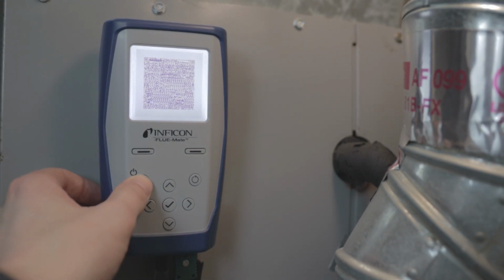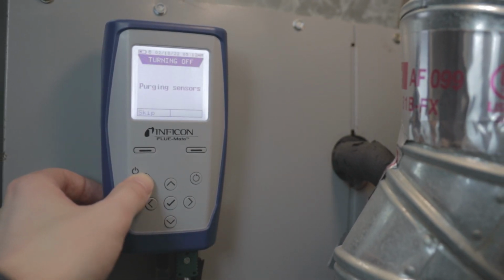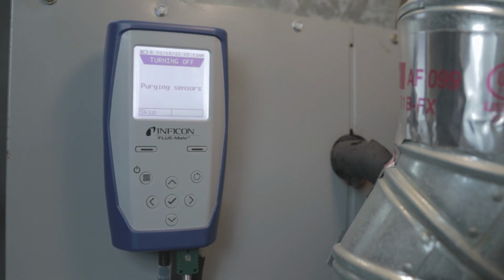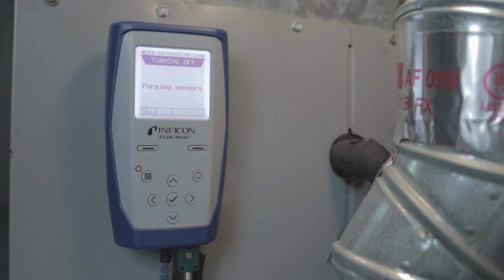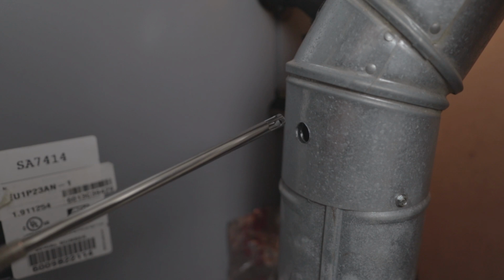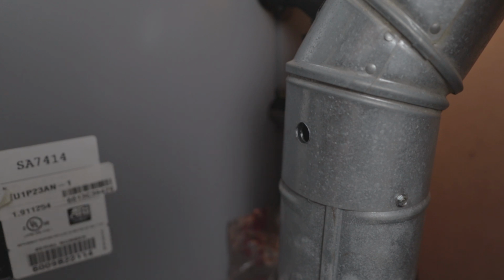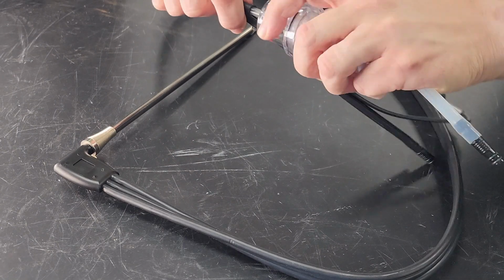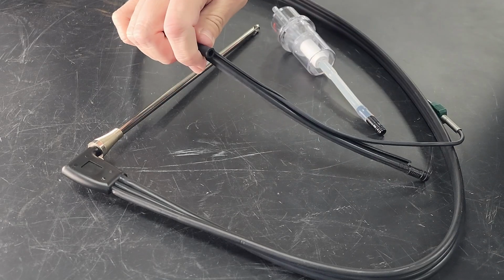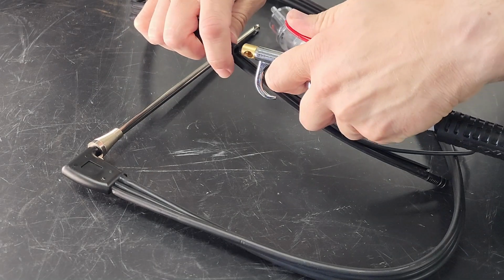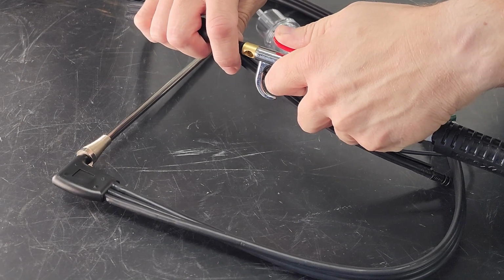Hold the menu/power button to turn FLUE-Mate off. A 60-second purge cycle will begin to remove any remaining flue gases from the instrument and hoses. Note that you should avoid turning FLUE-Mate off with the probe still in the flue. To remove any residual condensate, disconnect the hose from the water trap and blow clean compressed air through the probe.